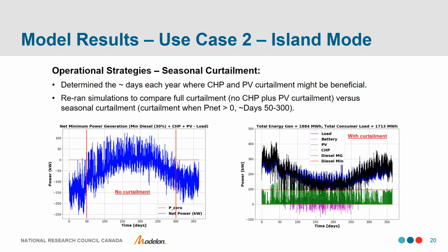Having now seen how operational strategies differ between seasons, we decided to run a full simulation for the full year to determine which days could potentially benefit from CHP and PV curtailment. In the bottom left, you can see that between day 50 and day 300, there is enough surplus power on a continuous basis that these days may benefit from operating with curtailment. And you can see what that looks like in the chart on the right.